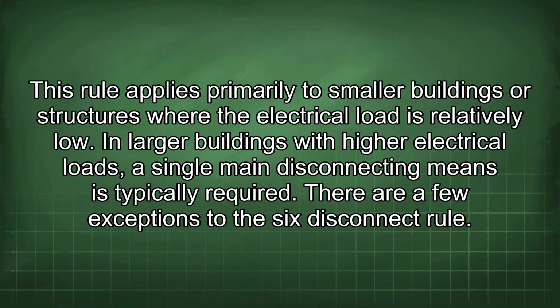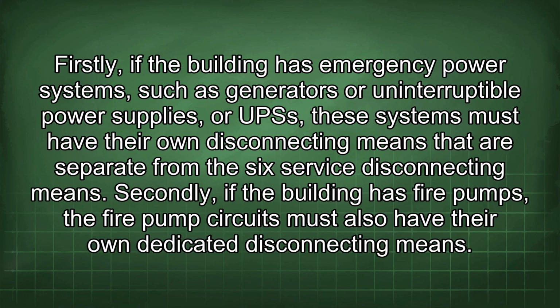This rule applies primarily to smaller buildings or structures where the electrical load is relatively low. In larger buildings with higher electrical loads, a single main disconnecting means is typically required. There are a few exceptions to the 6 disconnect rule. Firstly, if the building has emergency power systems, such as generators or uninterruptible power supplies, or UPSs, these systems must have their own disconnecting means that are separate from the 6 service disconnecting means.